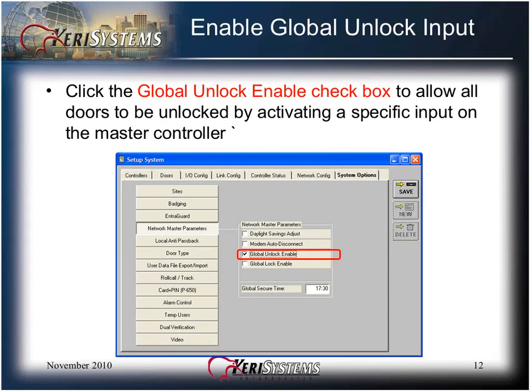Click the Global Unlock Enable checkbox to allow all doors to be unlocked by activating a specific input on the master controller satellite board. Note: Global Unlock Enable is not Fire Marshal approved to release all doors upon fire alarm activation.